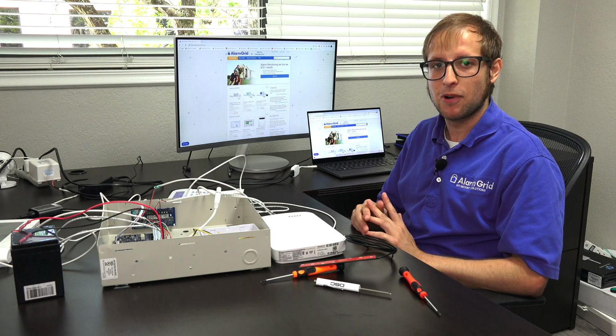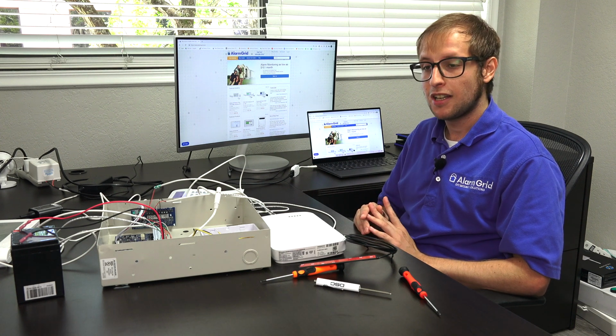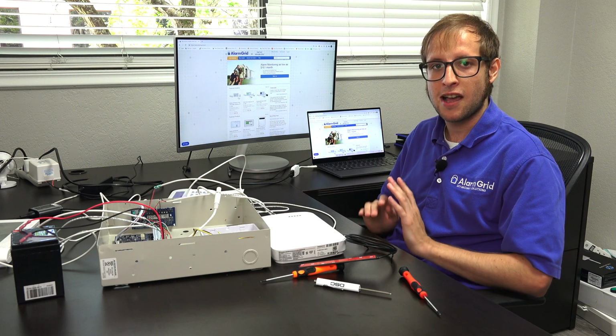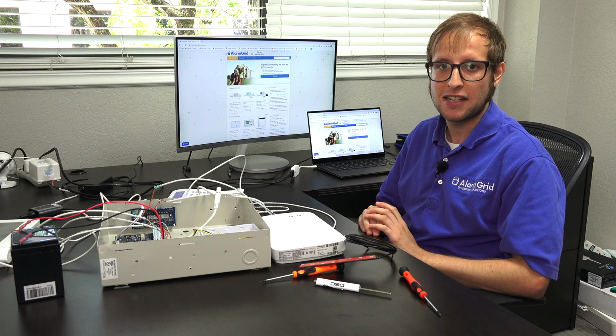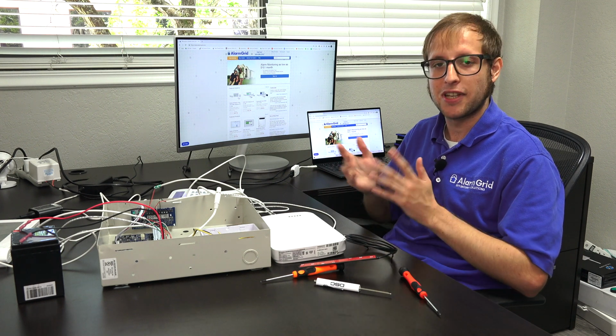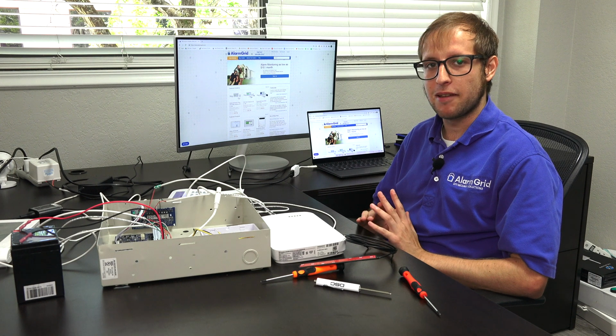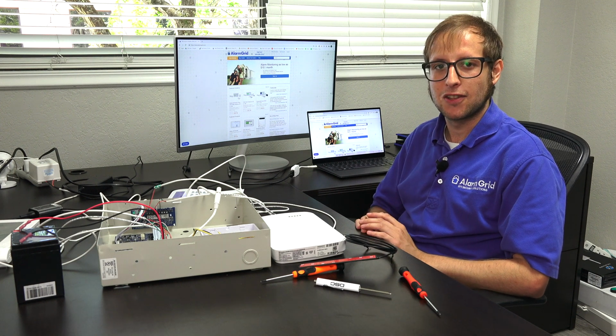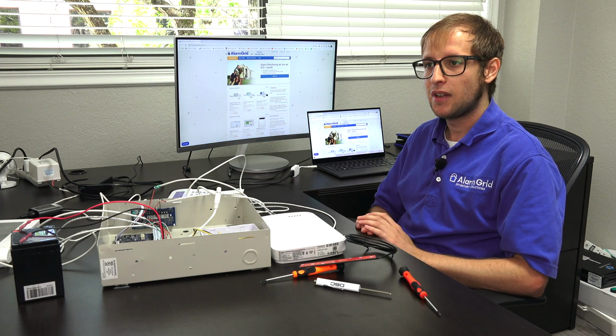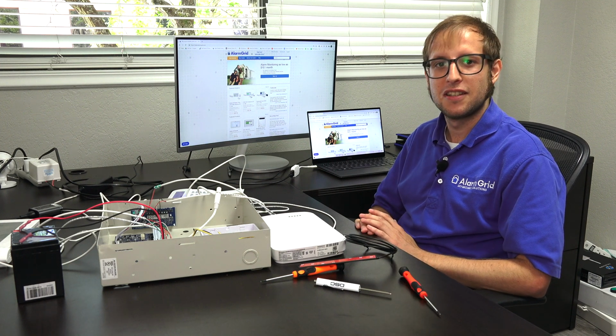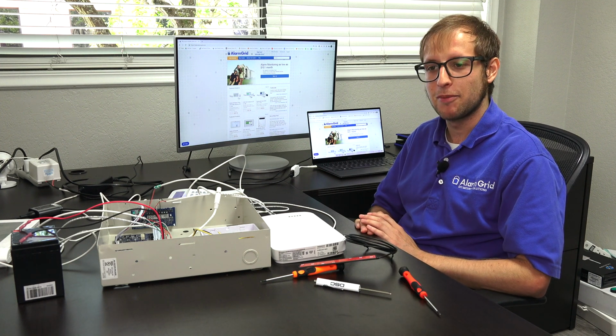You want to position it in a spot where you have the best cellular signals possible. It's a good idea to get the antenna as high up as possible, have it facing a tower if possible, a cell tower, that is, and have it away from any obstacles, such as large metal objects, thick walls. Just make sure you get the best signal you can. You can see how to check signals in the installation manual for the communicator.